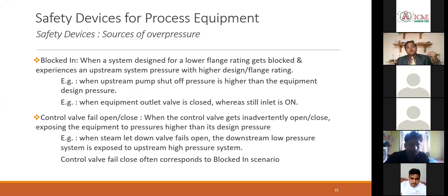And then if it is a pressure reduction valve, like from a high pressure steam, you are letting down into a low pressure steam system. So if that let down valve fails open, the entire low pressure system will see the high pressure coming in, and the low pressure system is not designed for a very high pressure because of, again, the economics. So at that time you need a PSV in the low pressure system to protect against this control valve failure.